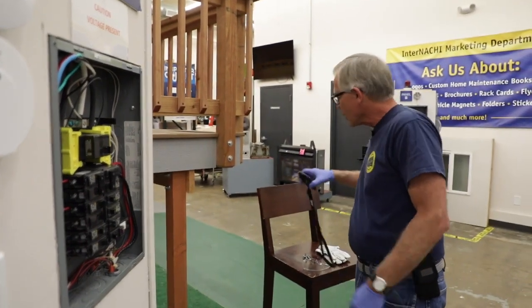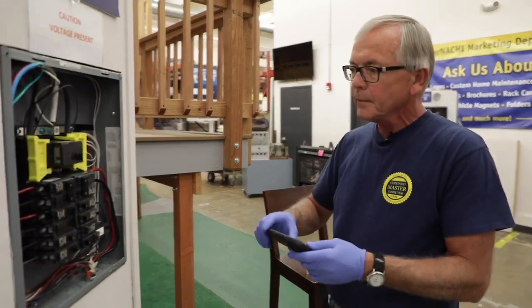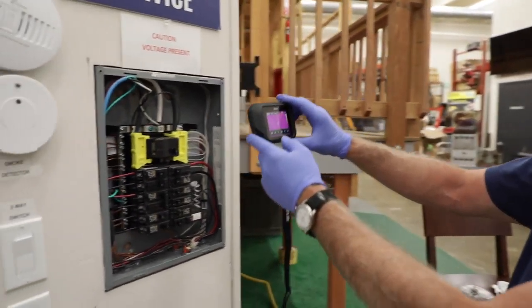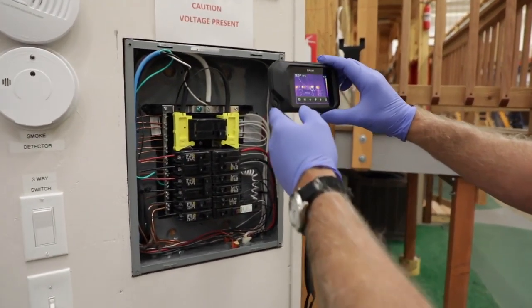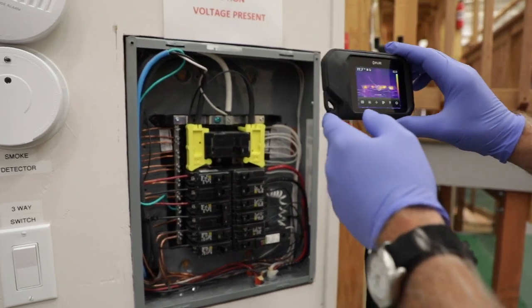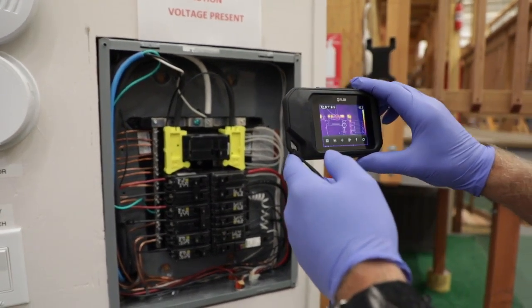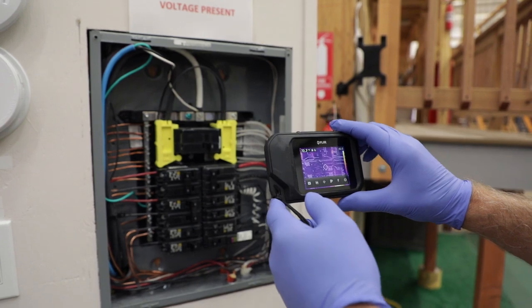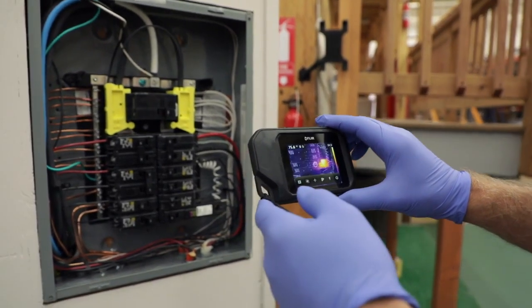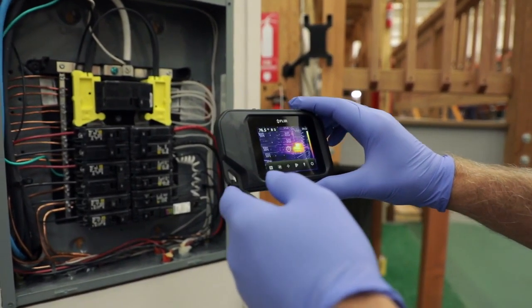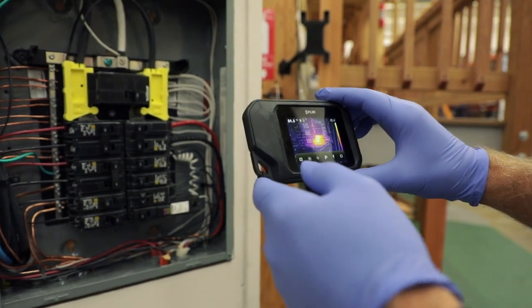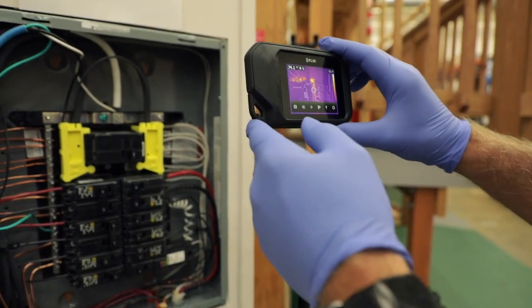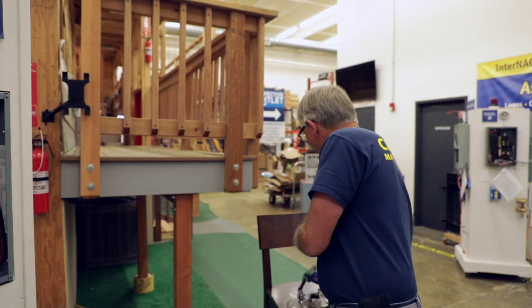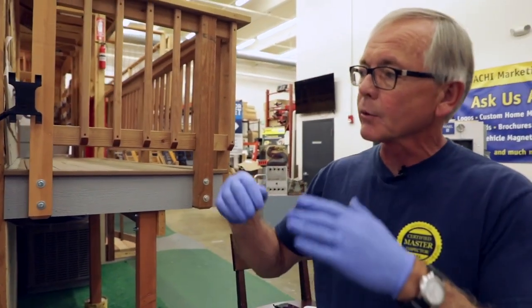Again, I'm going to go ahead and bring my FLIR camera back in. We're going to do another scan. I've got some warm lugs at the top. You get down to the bottom, there's my arc fault breaker right there. I'm not seeing anything concerning in here. Everything seems pretty normal. And then from that point, you want to go ahead and just conduct the rest of your inspection of the circuit breaker panel.